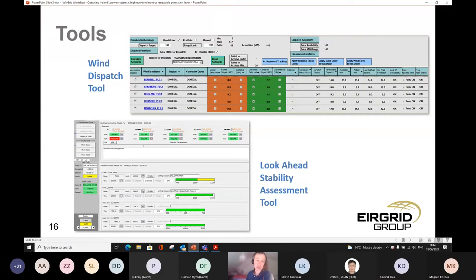But we've now introduced a look ahead element to it. So it's looking ahead up to 10 hours at what the system conditions will be, taking the output from the market management system as to what future conditions will be. And it's performing a full voltage and transient stability analysis of the system to basically inform us whether we are secure or not secure in that look ahead time frame. So that's recently introduced - it's a very critical tool for us to inform us, or to assure us, that we're continuing to run the system securely and to flag any look ahead issues that we might have on the system.